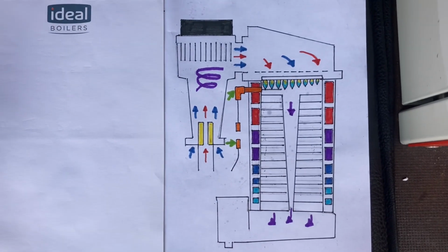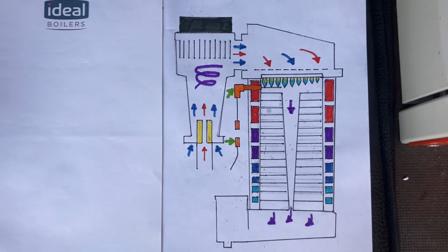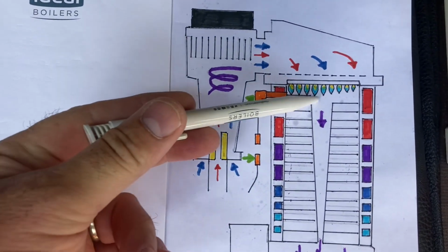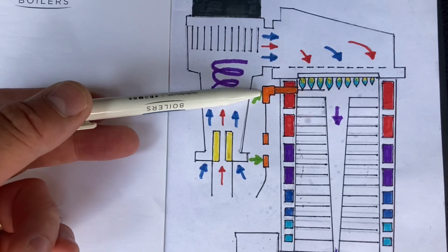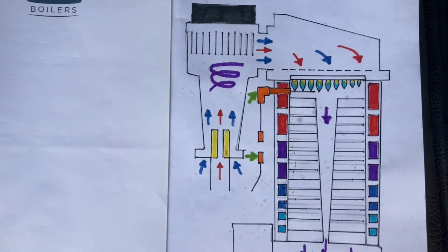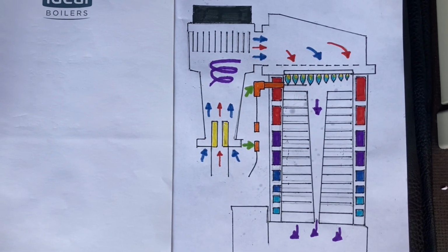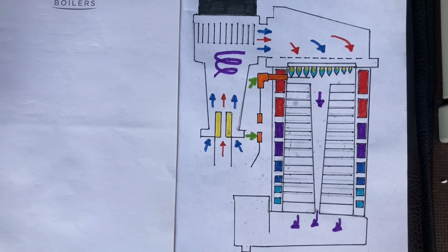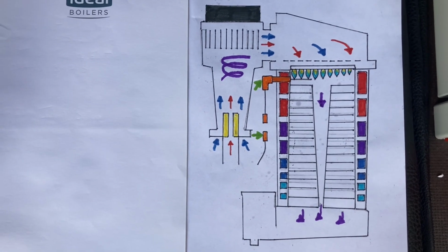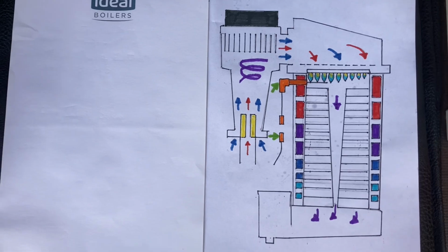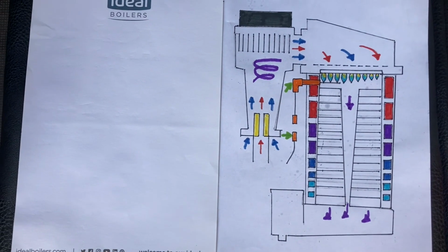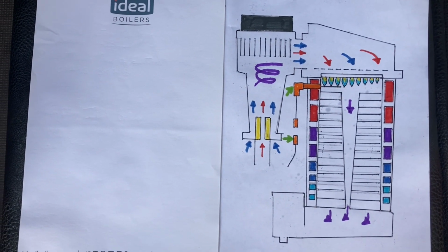enough about that. What I want to tell you about, and this is the detection probe, is what we're going to talk about here, and how we're going to test to see whether the burner's blocked and test the burner pressure through it. How this came about for me was I went to an Idealogic which was a year old. The hot water was just lukewarm, it wasn't getting hot at all.